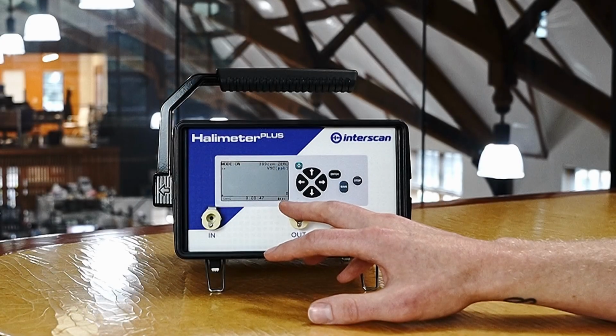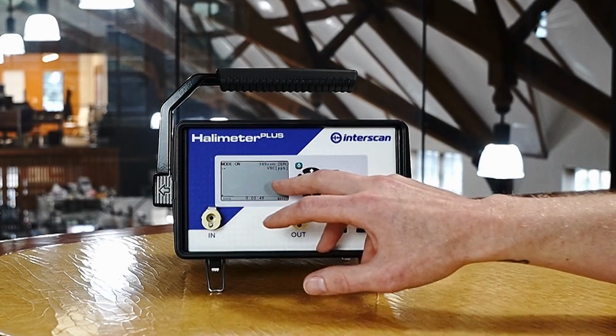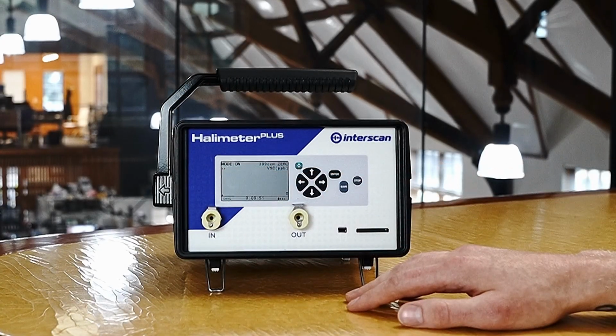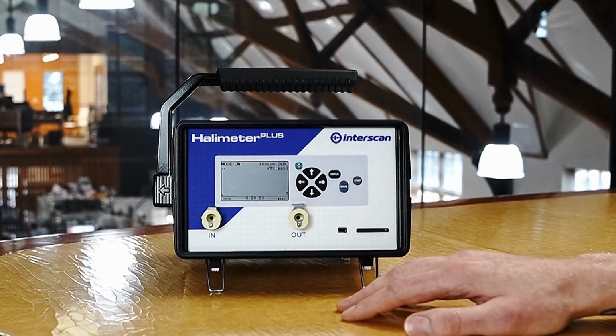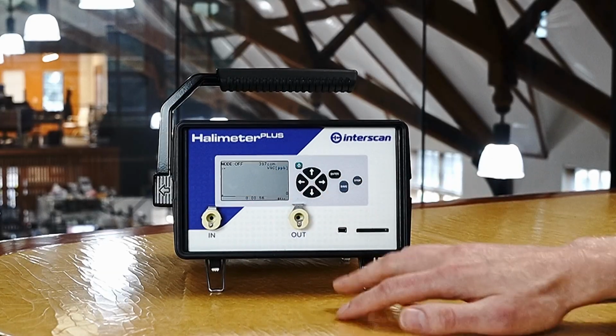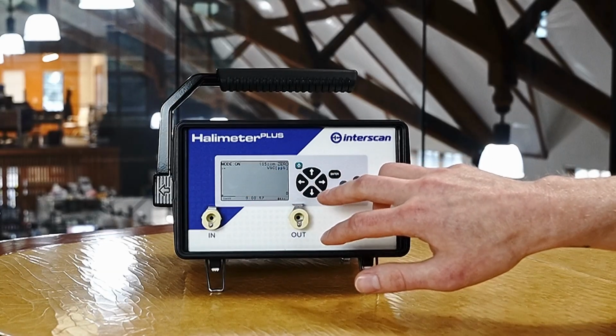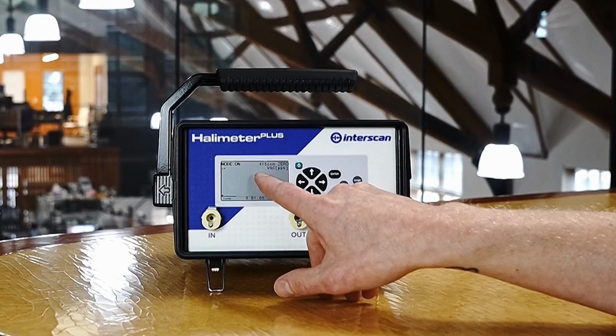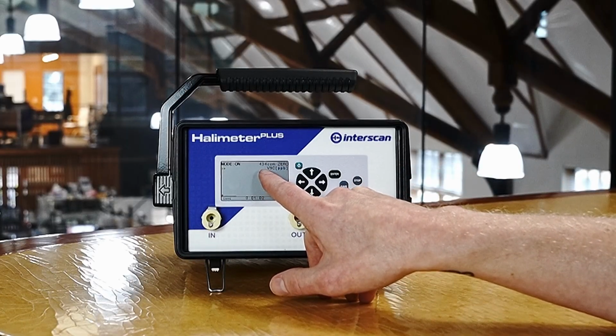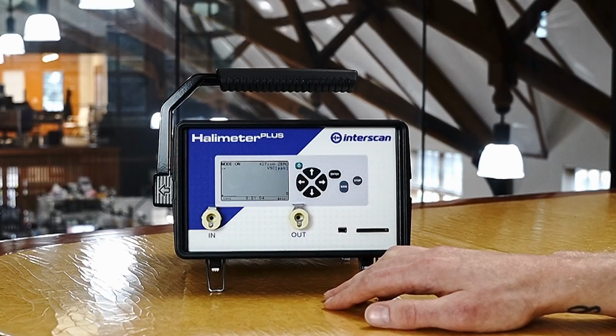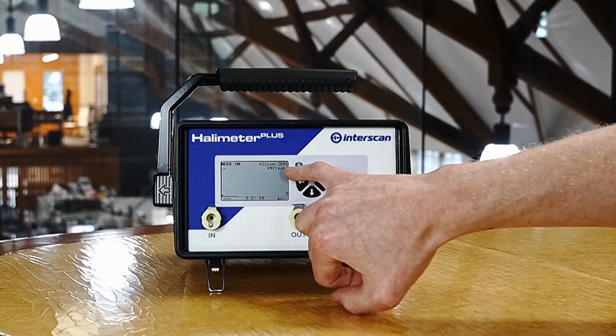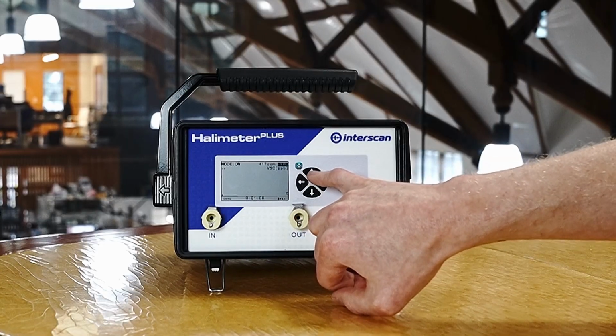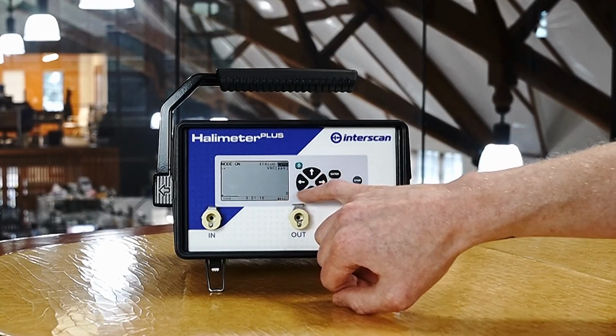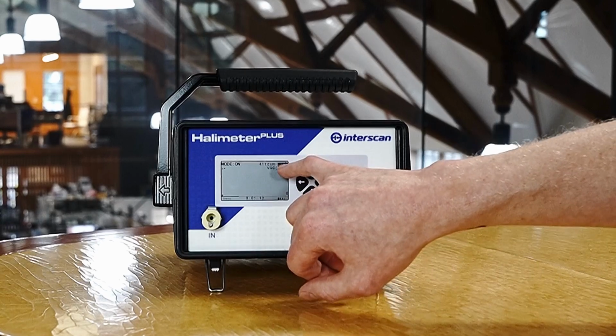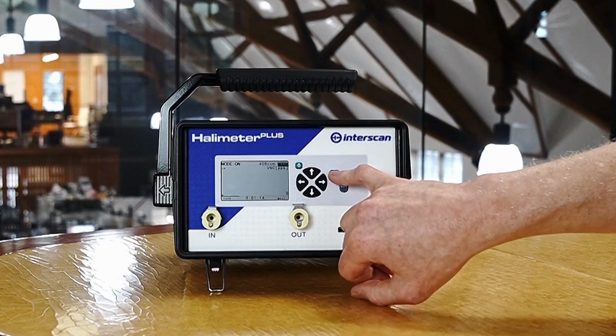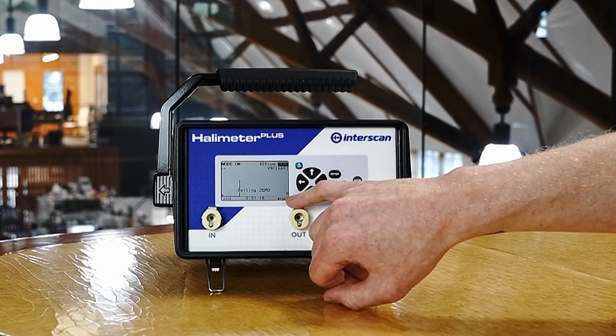Here in measurement mode, you can see all of the different fields. Mode in the top left tells you the pump is on. We can stop it by hitting stop, and turn it back on by hitting enter. You can see the values here in cubic centimeters, telling you how fast your pump is running. You have your zero in the top right, which allows you to zero the sensor if necessary. If you need to zero it, just press enter, and you should see values reappear.